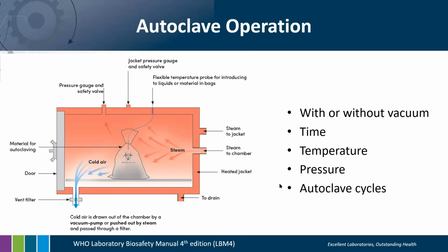This is required for loads such as waste bags, as represented in this figure, glassware, and other equipment where trapped air cannot reliably be removed by passive method. The more difficult air is to remove, the more pressure pulses will be required. What do I mean by that? As you see in this figure, you have steam coming in and air being removed.